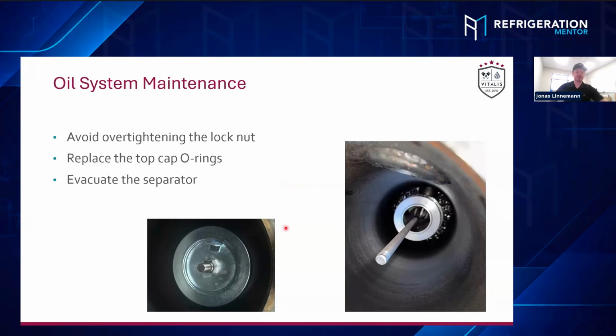And I've also seen a couple of times that these lock nuts on top of the cartridges get heavily over-torqued, bending down the top cap of the cartridge itself. I mean, the cartridge just has to sit tight, right? So it doesn't need a big torque. So that's something you should keep an eye on. What a coincidence. That's in the manual and says what it's supposed to be torqued to.